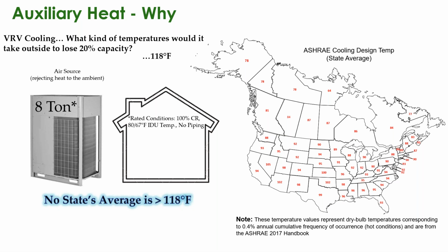So why are we talking about cooling when we're really talking about auxiliary heat? There's a tendency in variable refrigerant systems to just assume that they're a magic bullet and that oversizing isn't really a problem. Now, there's some truth to that. You can get away with it. They are incredibly flexible systems. But when you consider your cooling loads in some of these areas and what it takes to end up grossly oversized on the cooling side, which can create operational issues for equipment and reduce life cycles of these variable refrigerant systems, it doesn't take too much to get oversized on the cooling side.